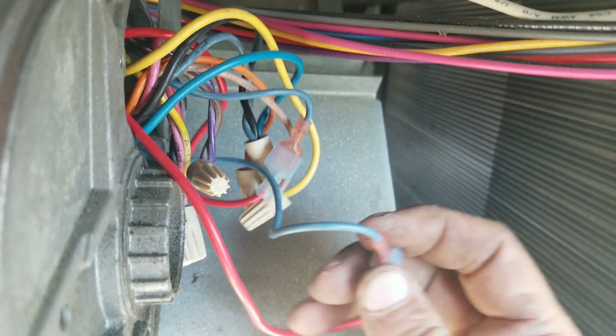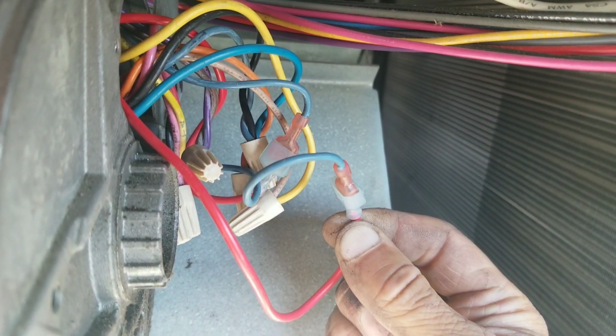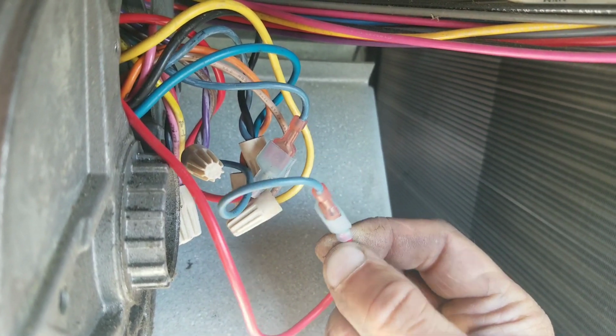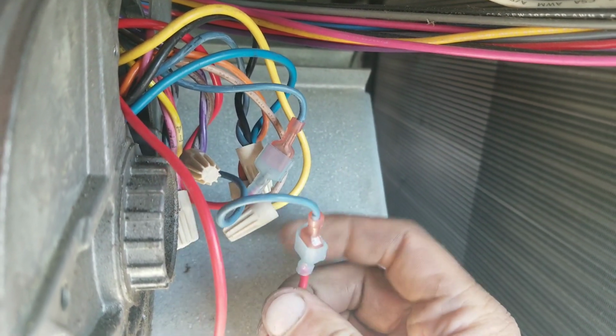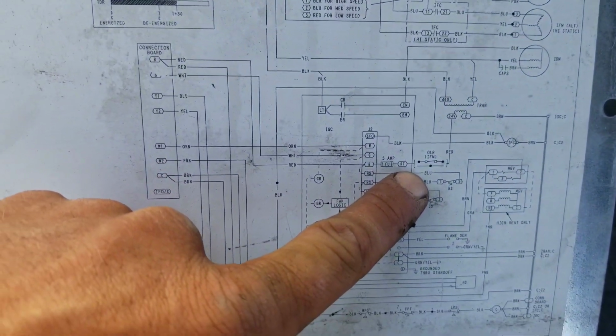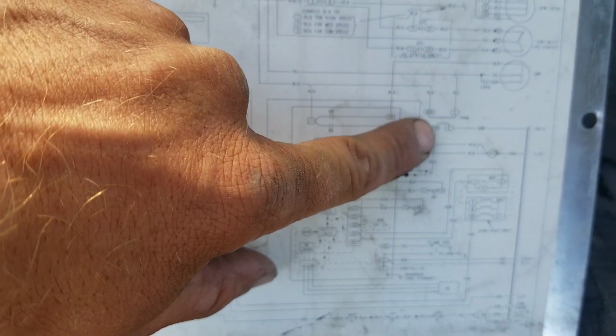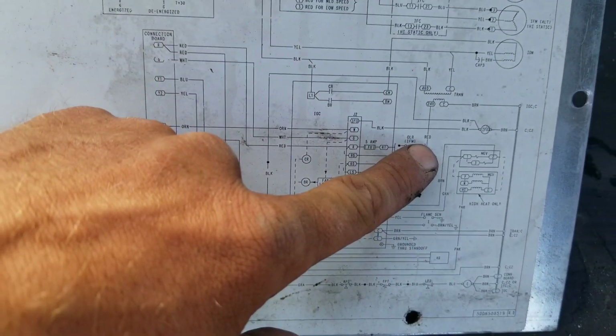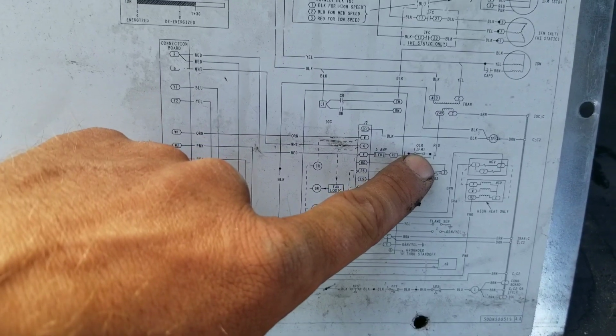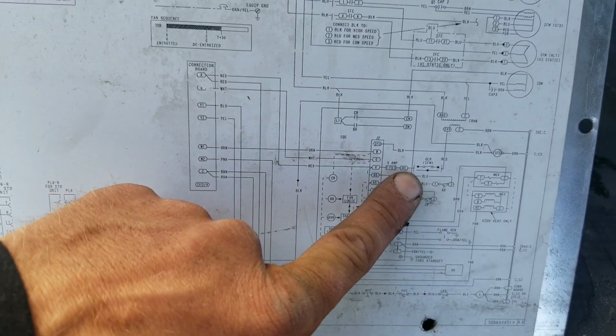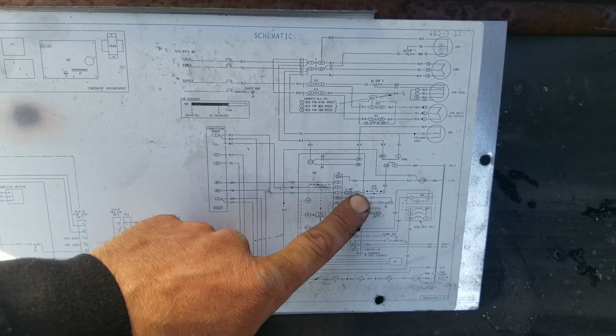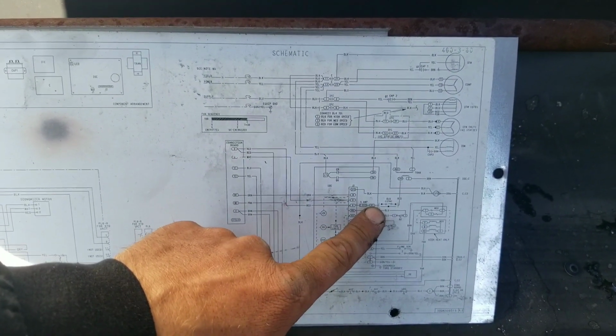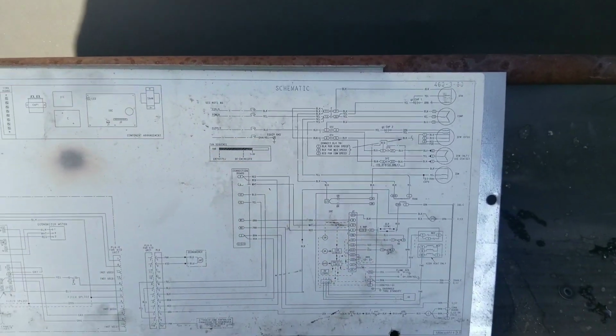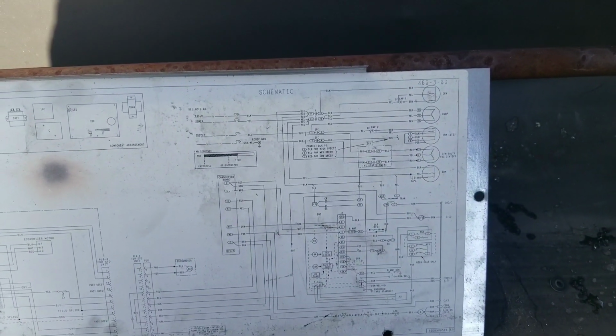On a side note, what was kind of confusing at first though, I checked this wire to ground and I had continuity. So I thought maybe that was my short to ground that I've been looking for. But if you come down here to our schematic, and we look right here on RT, that red wire that we were just looking at comes off of our 24 volt transformer, goes through our overload relay that's inside of our blower motor, comes out the other side, and then goes into our control board. Now, because it's low voltage control wiring, it is grounded. So once I figured that out, I knew why we were grounded. So that's not our issue.